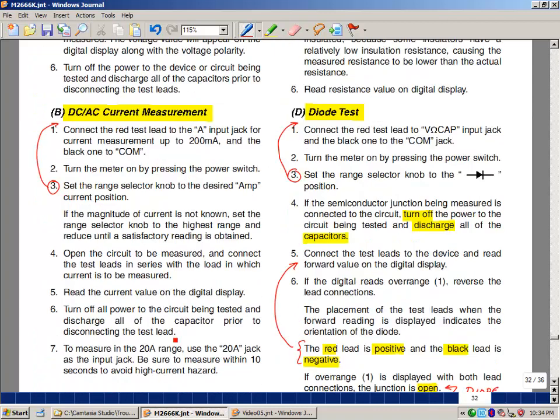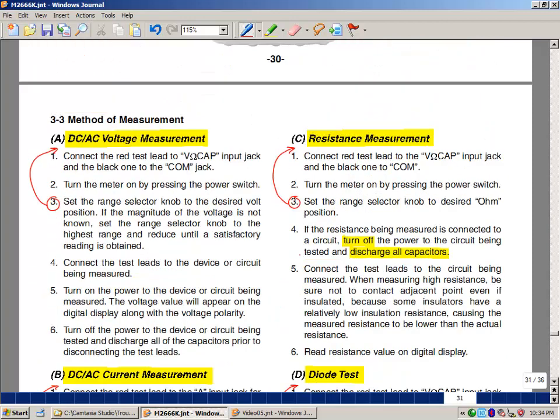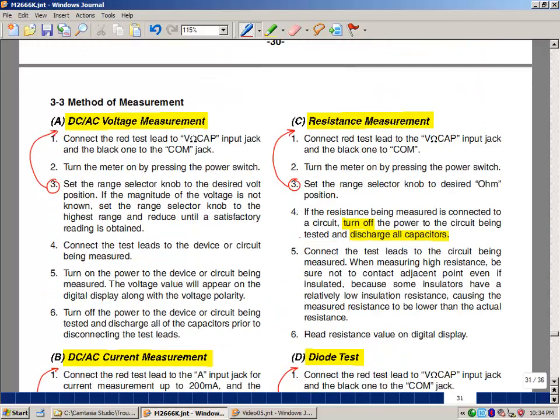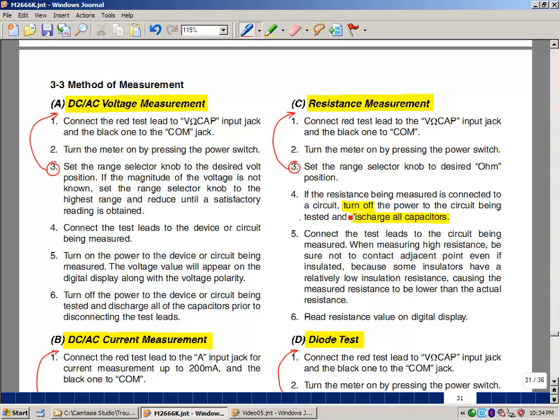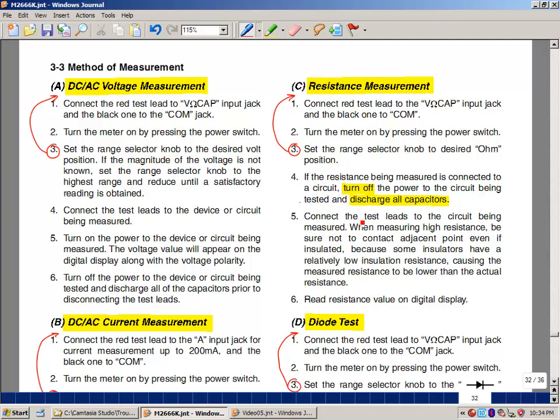Resistance measurement. Again I like to set the selector knob first. It talks about here measuring a resistance in a circuit. I wouldn't recommend doing that if at all possible but if you need to do that you should turn the power off in the circuit first and then try to discharge the capacitors. We'll talk more about this later in this troubleshooting class but capacitors can hold a voltage for a very long time. One way to discharge them is to put a low resistance across their terminals. You got to be careful because there can be an arc or a spark when you do that. I prefer that you test all resistors out of a circuit just like we were doing before.